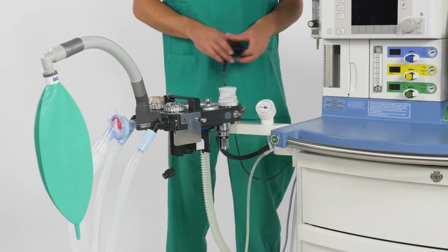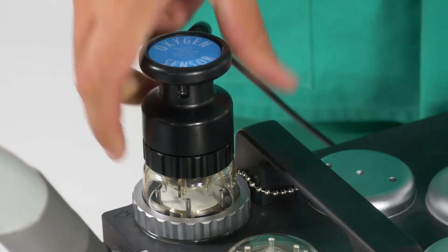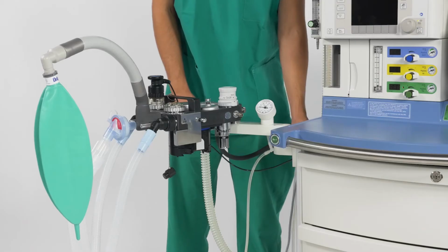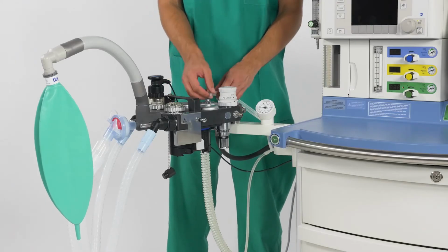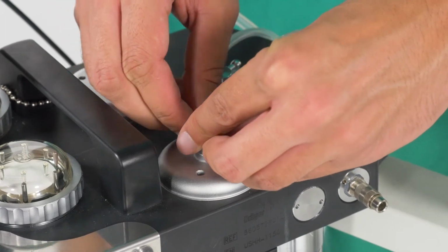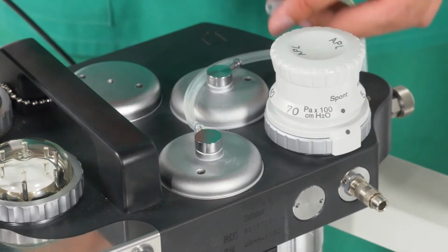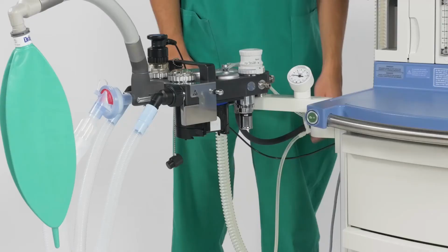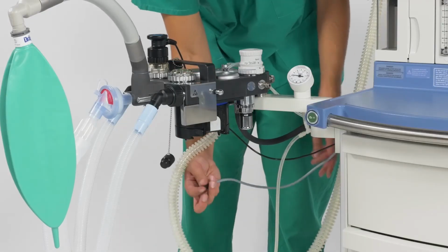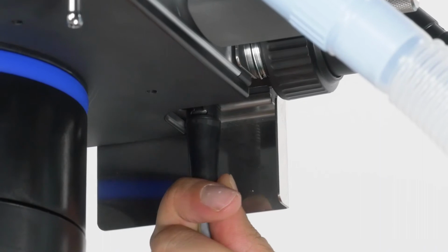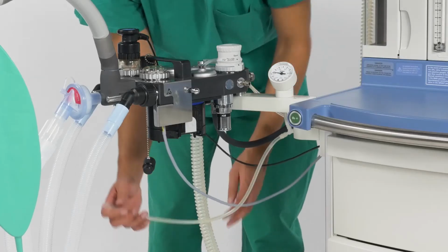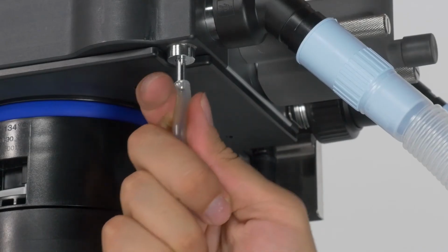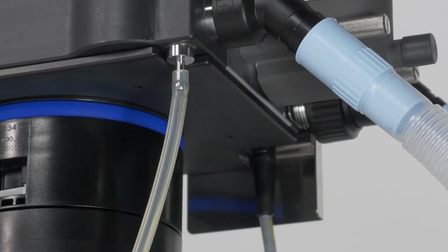Push the oxygen sensor into the opening on the inspiratory port. Plug the control hoses onto the connection port on the PEEP PMAX valve and the APL bypass valve. Connect the volume line cable and press the pressure measuring line onto the corresponding connectors on the bottom side of the COSY. Do not squeeze the pressure measuring line during installation.